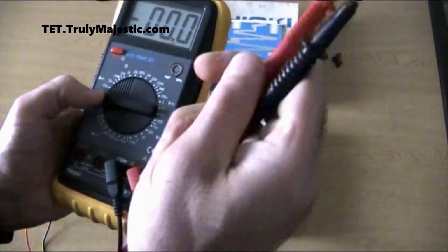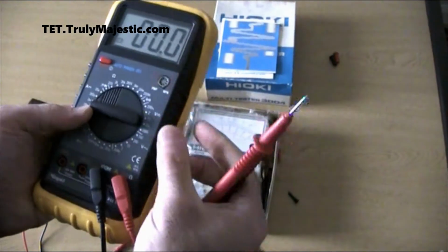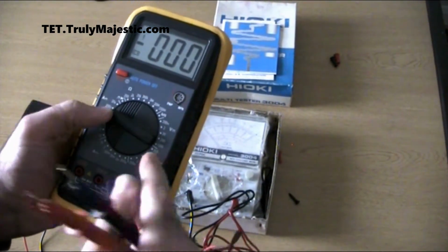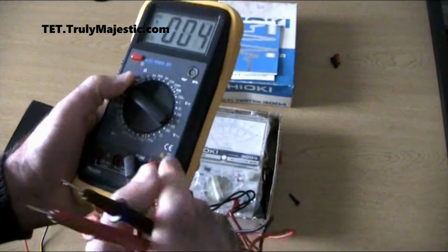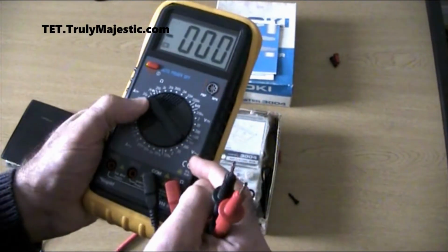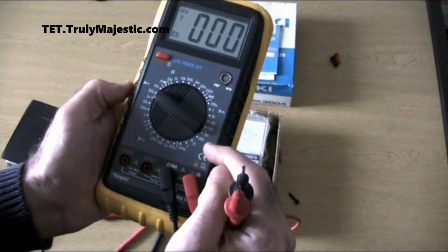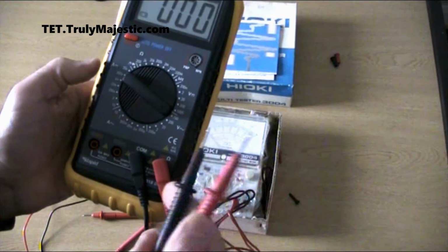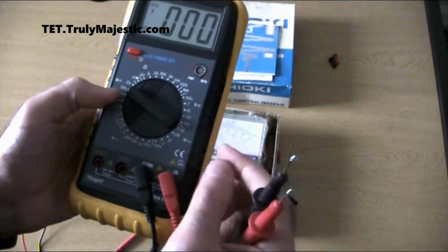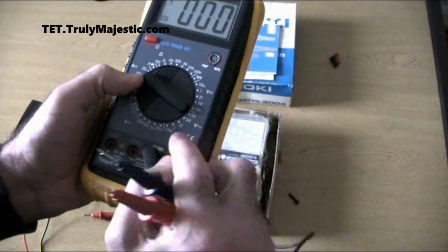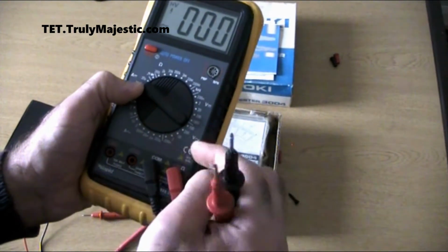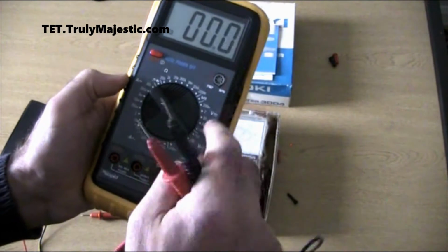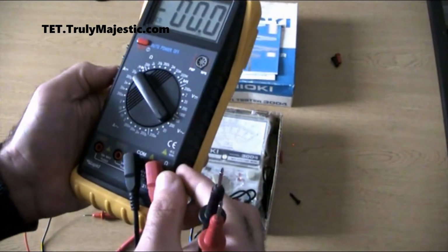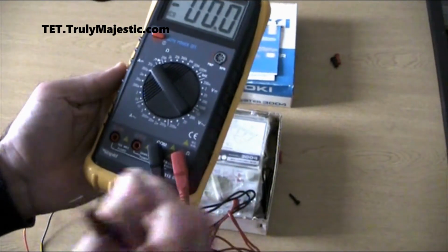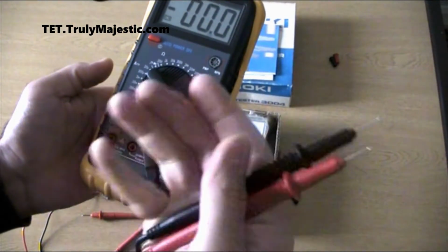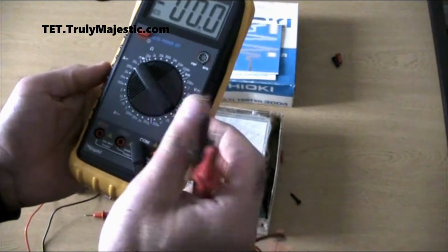With voltage, if I don't know what the voltage of that socket is, in a strange place, I start with the maximum: 1000 volt DC, or AC 700. That's my maximum range, so I'll measure with that. If it's showing smaller values like 100 or 200 volts, I can go down. But the next setting on my multimeter is 200, so if it's 250, I can't use that range, it'll damage my multimeter. So you're just choosing your selector as you measure, to get the most accurate measurement.